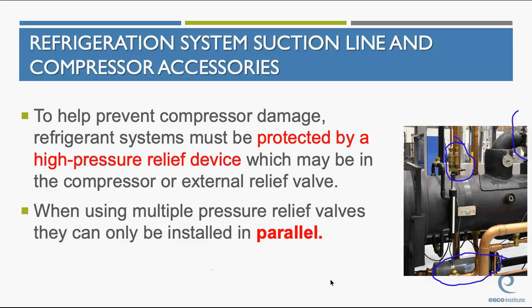Where does the material go when it leaves the pressure relief valve? Into the atmosphere. Remember what I said? If you ever have a refrigerant leak, get out of the area. Yeah. This is a classic example of it. Okay, relief valve should never open. Okay, there's something bad that's gone in here if a relief valve opens. Okay, but it's going to save a compressor.